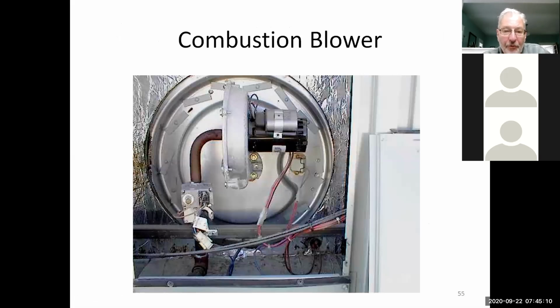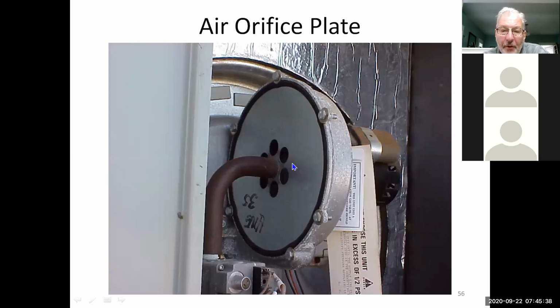So on these units, what you have is a drum type heat exchanger, and this is a power burner. We actually pressurize the heat exchanger with this combustion motor, and we mix the gas and air in the combustion chamber right here. Then as it hits the burner cone inside the unit, it fires off. So everything's pre-mixed inside this unit right here. Now, when you look at the unit, there are different air holes. Depending on the size of the burner, there might be 3, 4, 5 or 6 air holes in here. It all depends on the size of the burner, but that's designed to get a proper mixture of gas and air in this inducer and get it into the system so it burns properly, okay?